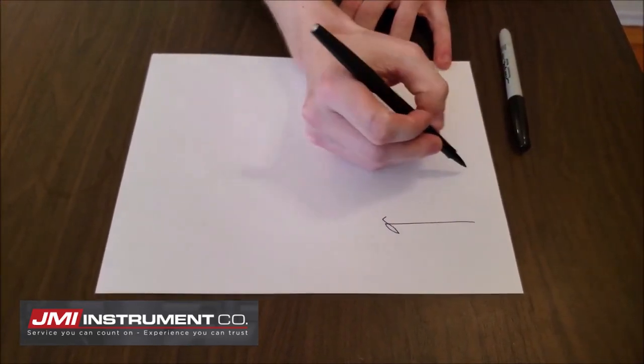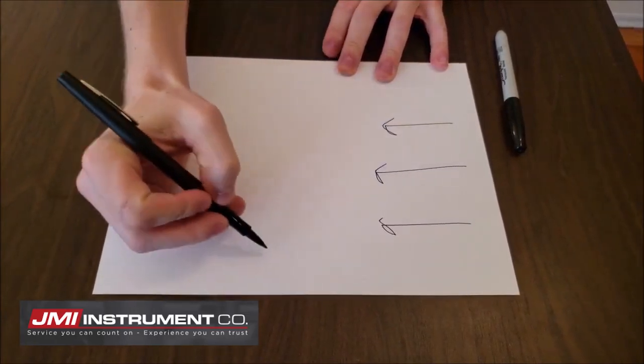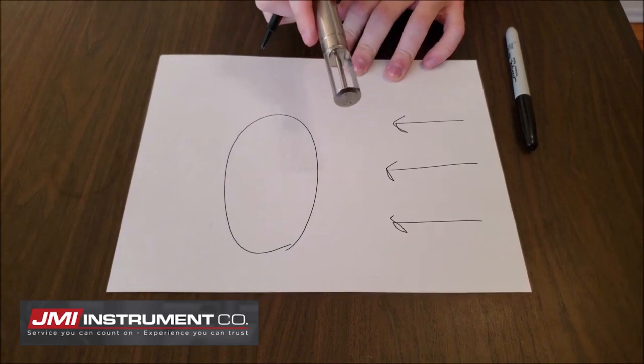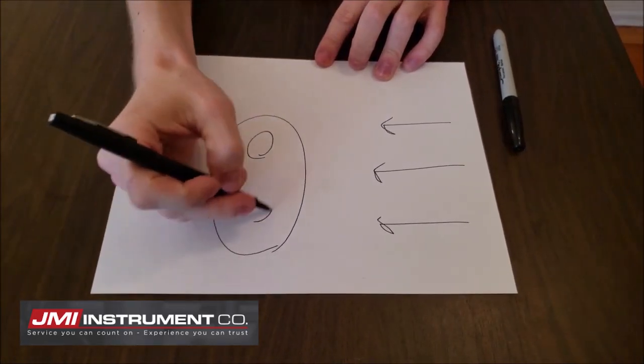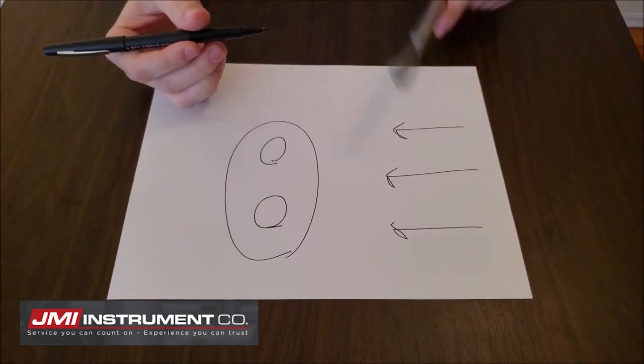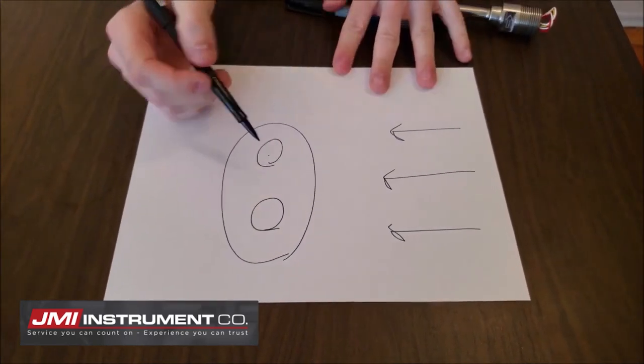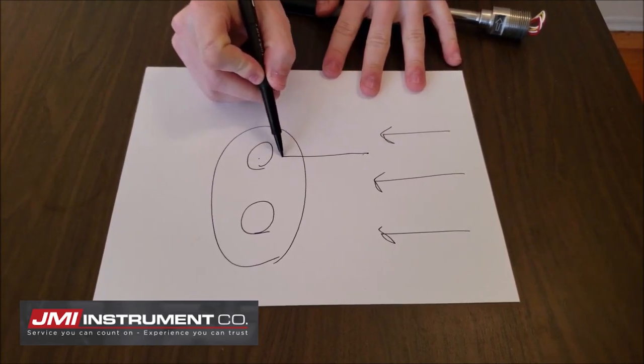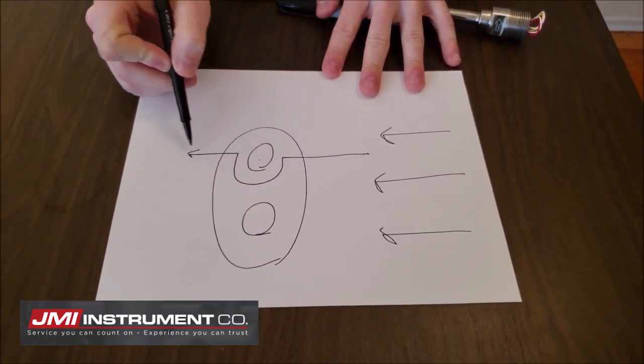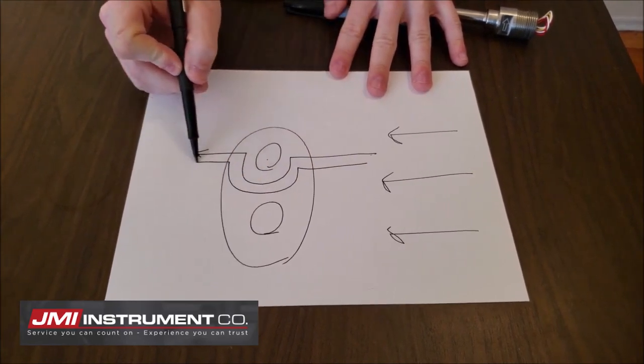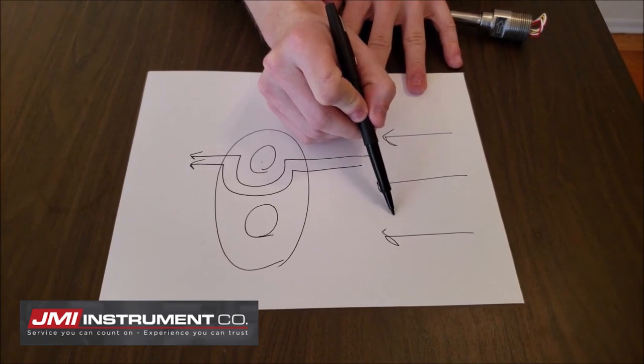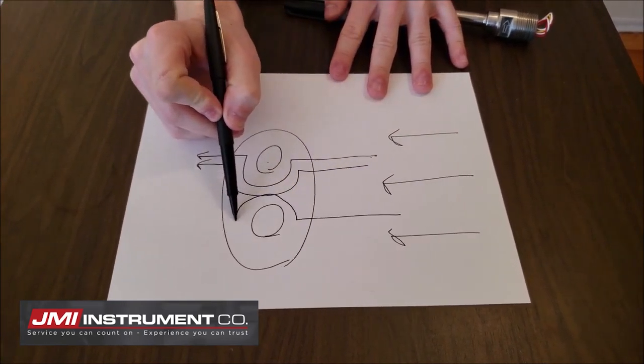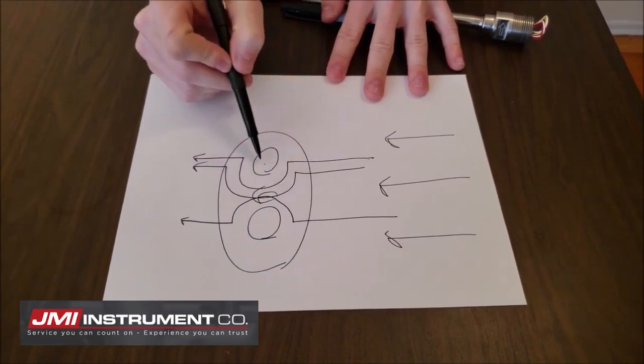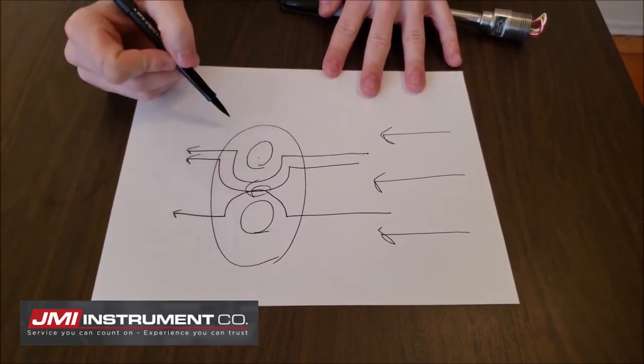What do I mean by that? If we take a look at just sort of an example of airflow, so we've got airflow coming in this way, right? And here is your probe, and you have 2 sensing elements in your probe. So just like the competitors' probes, these are going to look like this. Do you see how that works? Directly in line with the airflow. Well, if you take a look at where the airflow or the gas flow goes around these probes or these sensing elements, it's going to curve like that and go like that, right? And this line is going to do that, and so on and so forth on both sides. Take a look at this here. This one is going to curve and hit the airflow of the other sensing element. These are going to interfere with each other.